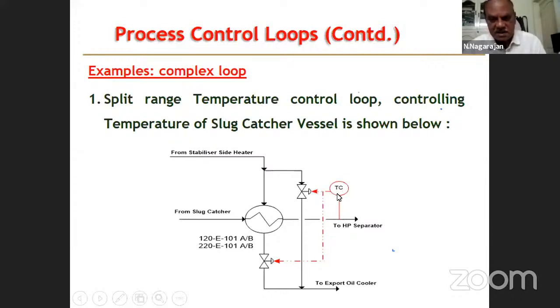For a certain range, maybe half of the range, it will be directly controlling this one. Main thing is you have to regulate the hot stream. For one half it may be directly acting on this control valve and regulate the flow rate of this valve. But suppose it is exceeding, as I said in one example, when the hot oil temperature is going more than 150, what do we do? We bypass a cold stream and mix it with the outlet stream so that you achieve the required temperature here. This is the bypass control. So one controller is operating two control devices. This is the split range control.